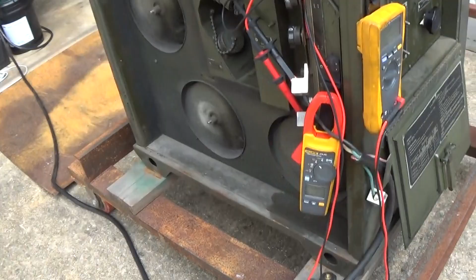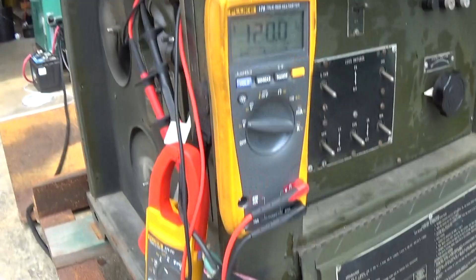Should be warm enough here. I'll turn the master switch on — got our cooling fans going, and the cooling fans alone draw 2.8 amps. I forget what this thing is rated at, let me go look real quick. The nameplate's on the air filter cover — 26.7 amps rated.